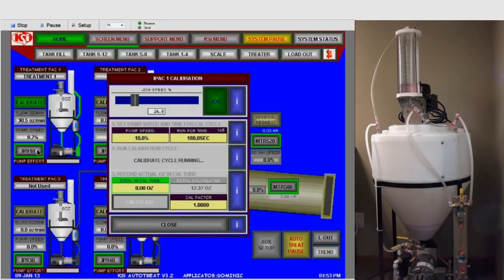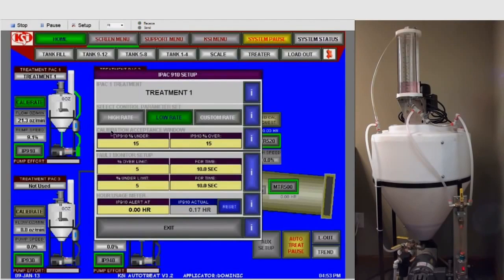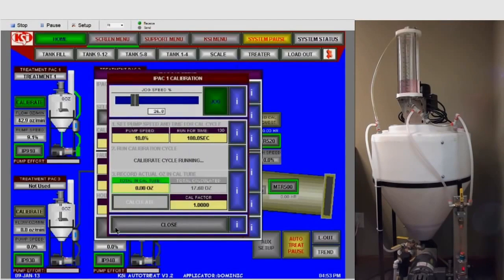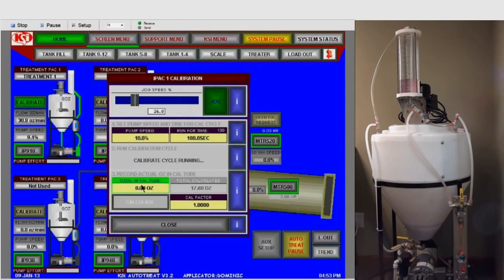If you recall earlier, when we were in, I'll just select this pump. If I click this cal pump, we talked about this IP910, this calibration acceptance window, 15% under and 15% over. I'm going to exit out of this. This, when we're doing a calibration process, is where that comes into play, this right here.